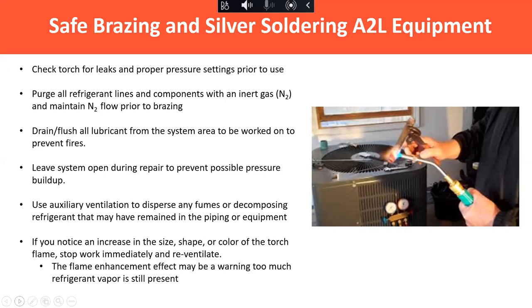You should not be using that to leak detect. We want to use regular leak detectors. And if you do notice any flame enhancement, that's really telling you you probably don't have good enough ventilation. So you should shut down that work and redouble down on ventilation and purging to make sure, because any refrigerant you have there, it gets in a flame, it can generate some decomposition products, some acid compounds that aren't particularly nice. You're not going to want to get those up your nose or breathe those in. Okay, can we go to the next chart, please?